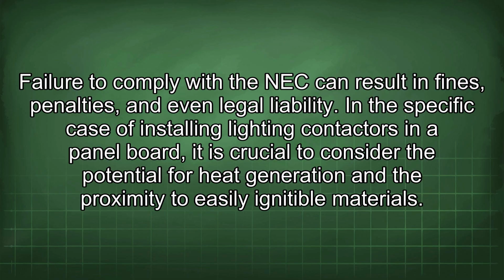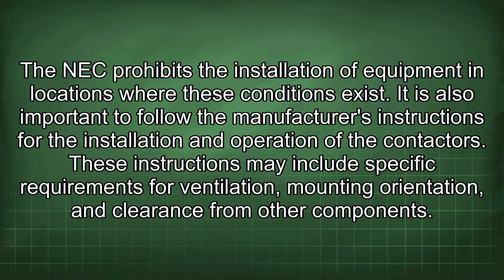In the specific case of installing lighting contactors in a panel board, it is crucial to consider the potential for heat generation and the proximity to easily ignitable materials. The NEC prohibits the installation of equipment in locations where these conditions exist. It is also important to follow the manufacturer's instructions for the installation and operation of the contactors. These instructions may include specific requirements for ventilation, mounting orientation, and clearance from other components.